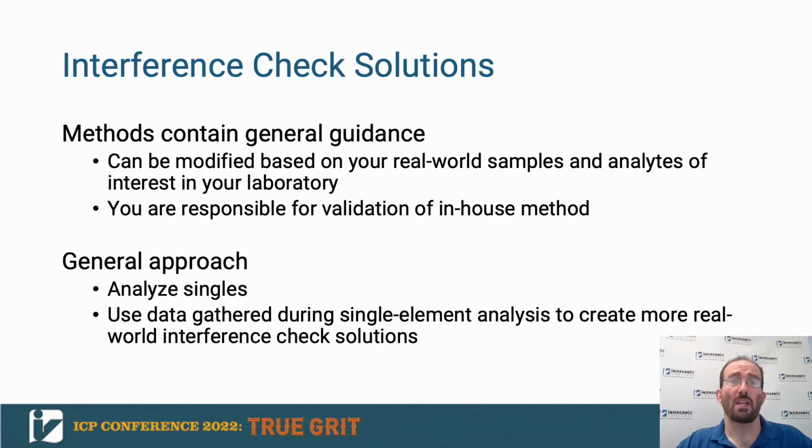There are ways to help you take into account these interferences before you even start looking at your data. Interference check solutions allow you to see exactly how the elements are interacting with each other without the added headache of trying to figure out your concentrations in an unknown. The methods have general guidance on the composition of interference check solutions, but advise that these can be modified depending on which analytes your specific laboratory is analyzing.